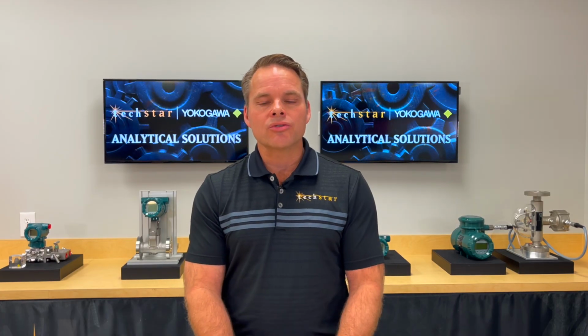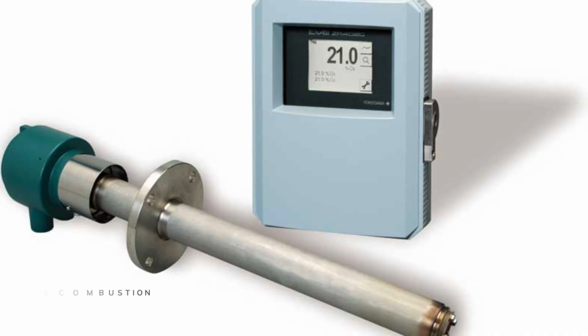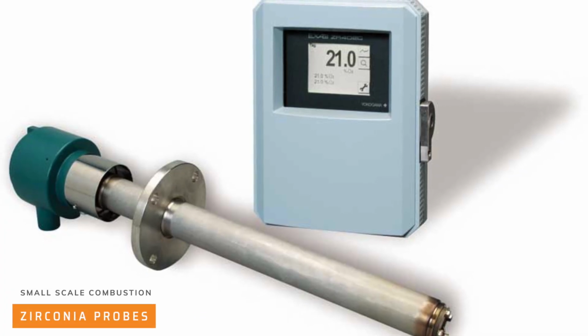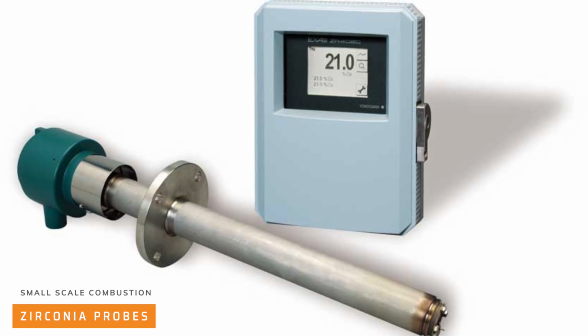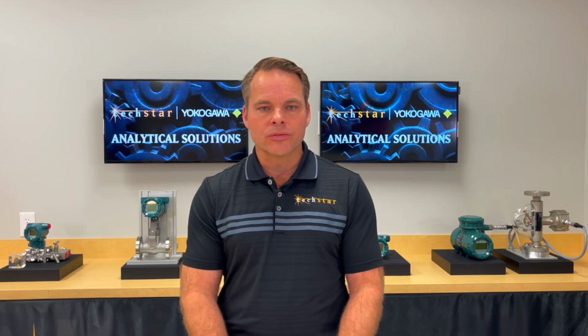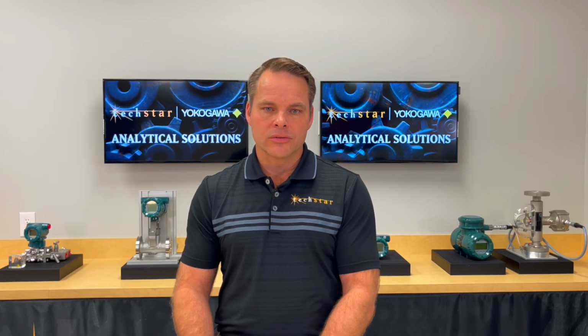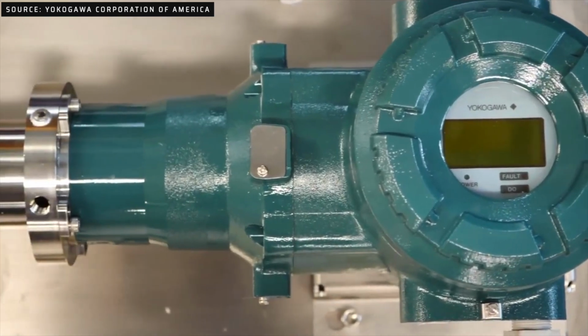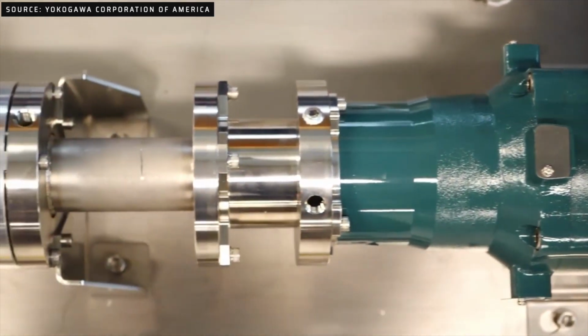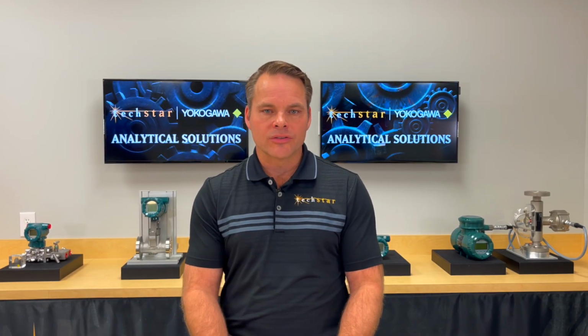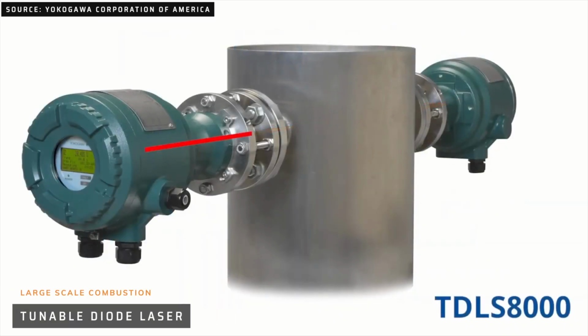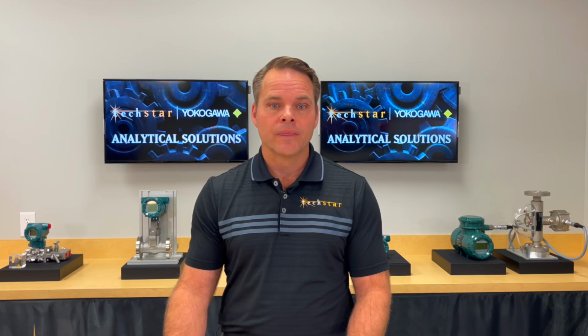That being said, we would traditionally use zirconium oxide-based oxygen analyzers to measure either in situ, where the sensor's inside the heater, or as the temperature increases, we would use a close-coupled extractive analyzer. With the advancements in technologies, we now have a probe-style TDL for lower temperature combustion to measure CO, O2, and/or methane. We also have high-performance line-of-sight cross-duct tunable diode lasers that can measure O2, CO, and methane from the startup conditions all the way to the high-performance furnaces up to 1500 degrees C.